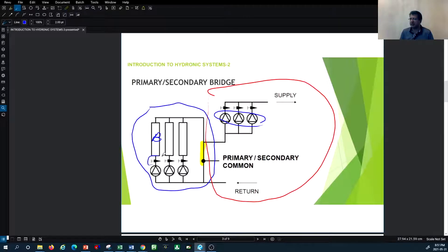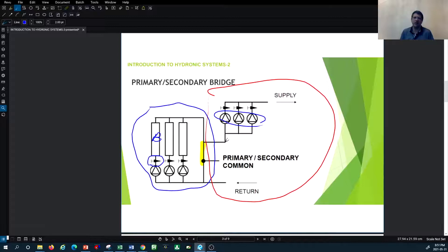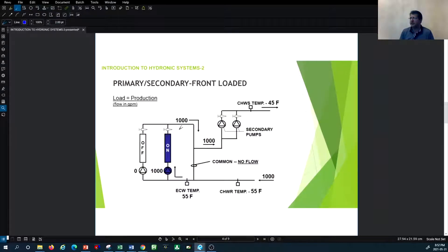As shown schematically, these are isolation valves — in real construction you must provide isolation valves on both sides of the pumping system, whether for the primary or secondary loop. You also need to provide a bypass line, which we will cover in more detail in a future tutorial. Moving along, we have the primary line with two chillers — one is running and the other is offline.